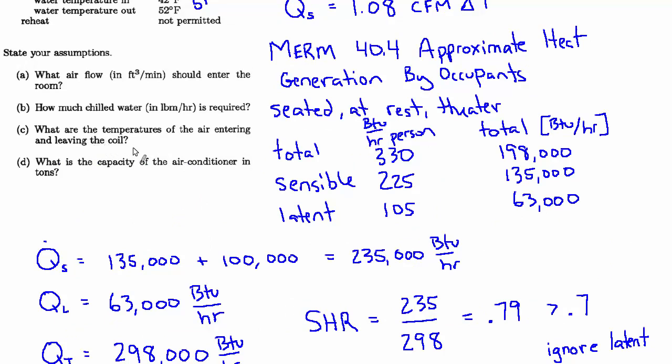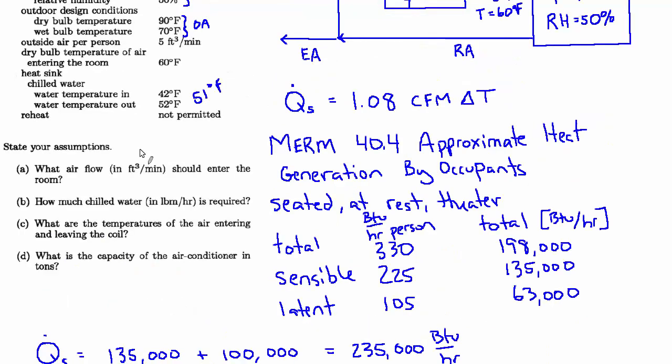leaving the coil? I think we have to get realistic and say it's not 60 degrees. It's much lower than that. So we could debate whether it's 51 or 46 or 44, but it's definitely lower than the dew point. And I'll leave it to you to pursue that further if it's of interest.